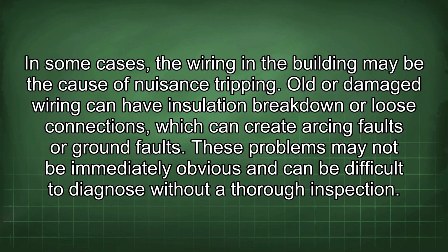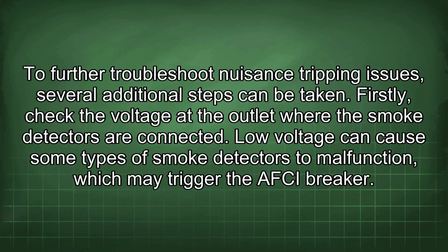Old or damaged wiring can have insulation breakdown or loose connections, which can create arcing faults or ground faults. These problems may not be immediately obvious and can be difficult to diagnose without a thorough inspection. To further troubleshoot nuisance tripping issues, several additional steps can be taken. Firstly, check the voltage at the outlet where the smoke detectors are connected. Low voltage can cause some types of smoke detectors to malfunction, which may trigger the AFCI breaker.